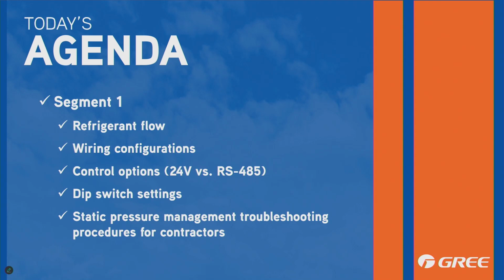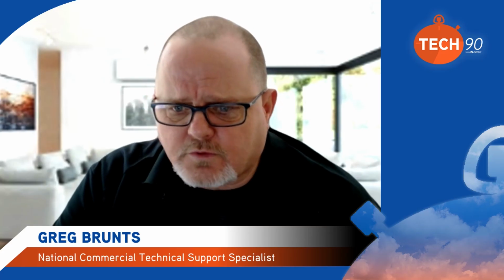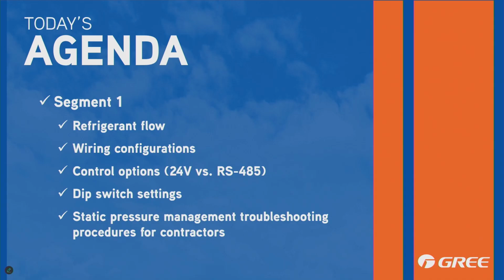We're going to cover dip switch settings for airflow if you're using 24 volt. If you're using the GREE controller and it's using RS485, it becomes variable speed at that point. You don't have to set the dip switches for airflow. We're going to talk about static pressure measurement, troubleshooting procedures for contractors, and verifying the airflow after we got our airflow set up.